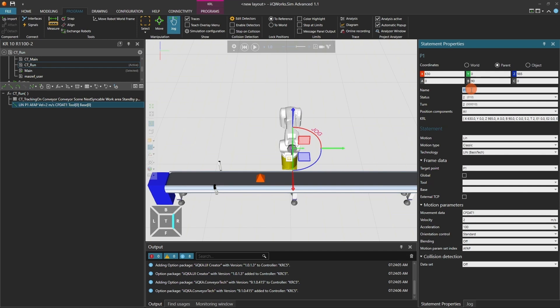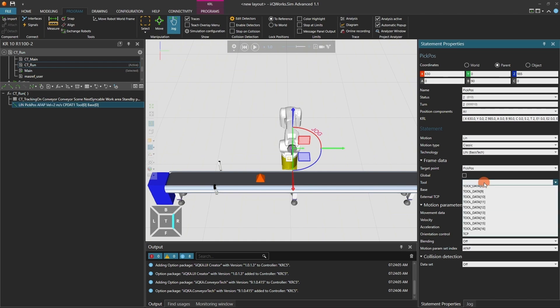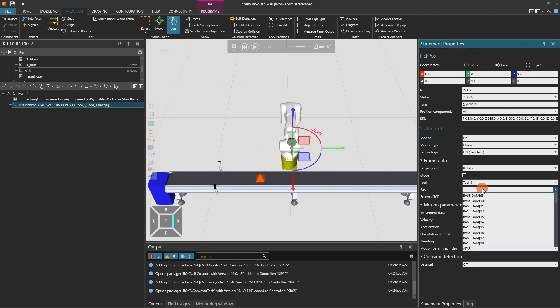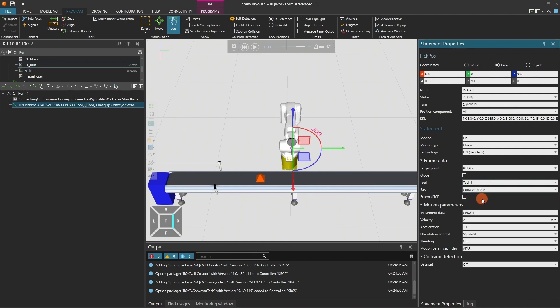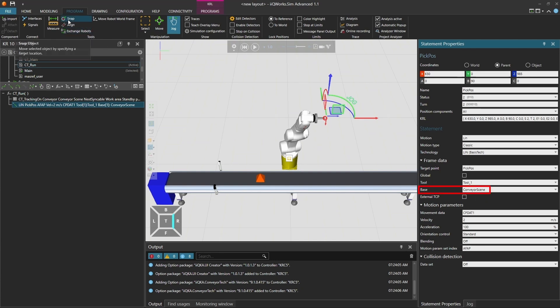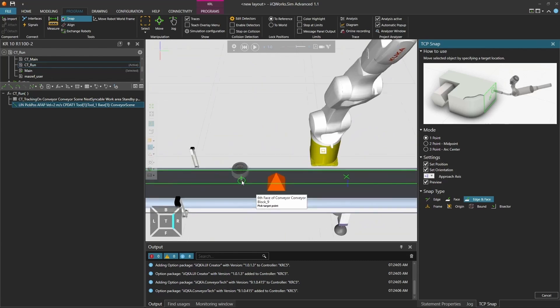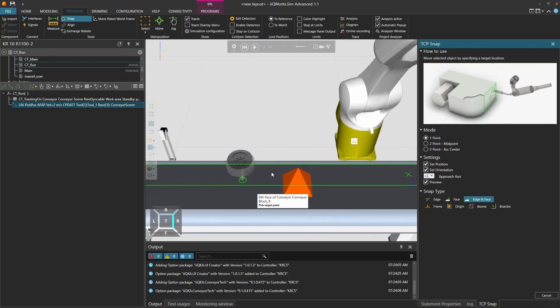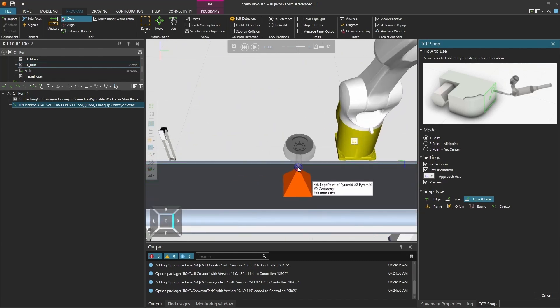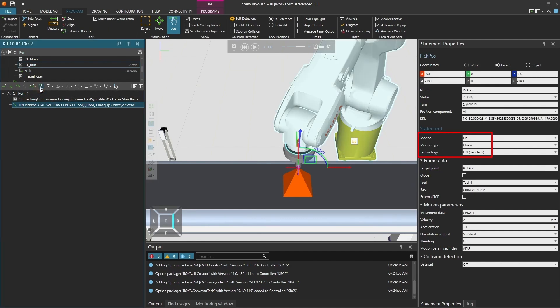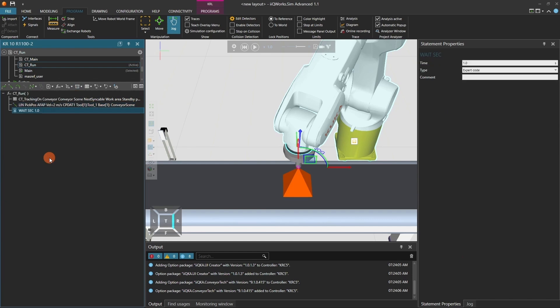Now add your program logic between CT tracking on and CT tracking off. For example, add a linear motion to a pick position and a wait statement of 2 seconds. And make sure to select the base, conveyor scene, if the robot should synchronize its motion with the moving part. Add a wait for statement to define the time the robot should follow the movement of the part. Again, make sure all positions are LIN classic motion. No PTP or spline motions are allowed.